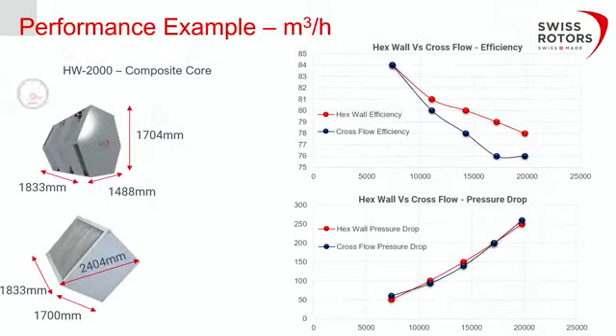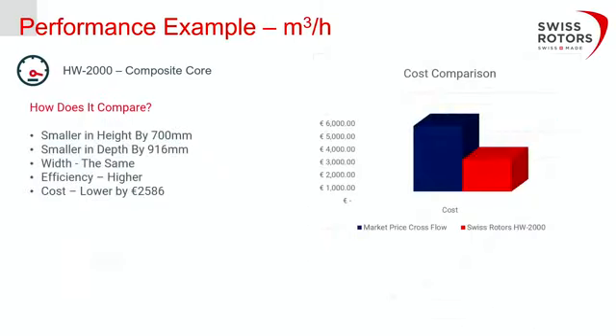When we start to get towards the HW2000, towards this top end of the range, this is where the savings really start to increase. So again, higher level of efficiency, very similar pressure drop all the way across the range, but look at the size differences now. So we're in the height difference of 700 millimeters lower in height, nearly a meter shorter for your air handling unit. Now when we start to look at the cost, there's a 2,500 euro cost difference between this and a comparable cross-flow heat exchanger.